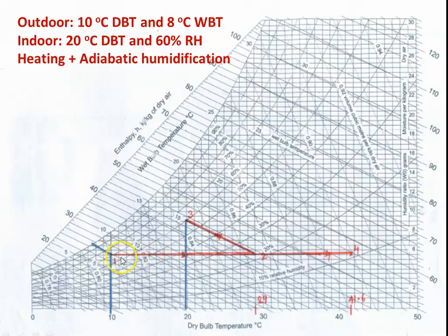Draw a horizontal line from point 1, then draw an inclined line parallel to the enthalpy line using the scale — this meets at point 2. So the process is heating (1 to 2) then adiabatic humidification (2 to 3). During the heating process, temperature rises from 10°C to 29°C. Then during adiabatic humidification, water is sprayed — temperature decreases and moisture content increases.